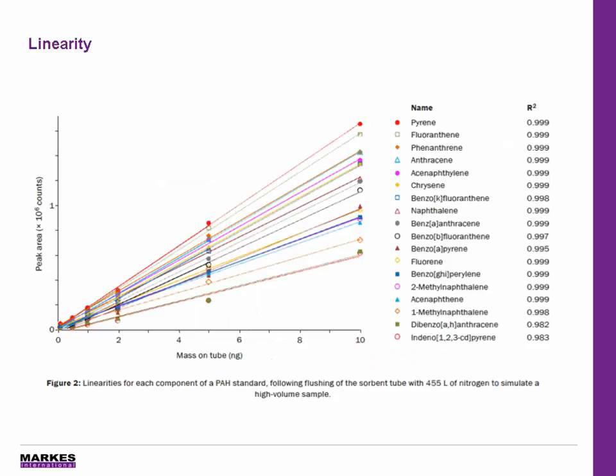As with all thermal desorption analysis, it's important to assess linearity. Linearities were calculated using five tubes loaded with the PAH standard at a range of 0.1 to 10 nanograms. The tubes were also flushed with 455 litres of nitrogen to simulate high-volume sampling, and the linearities were excellent — all R-squared values were found to be above 0.98.